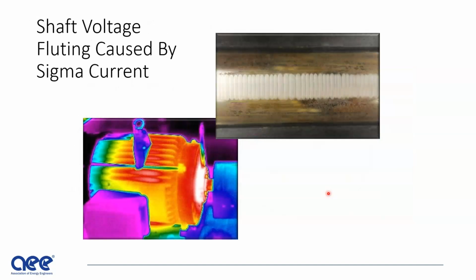This is an example of what it looks like when you have shaft current. Here you see a bearing that is running very hot, and it's because of this race inside the bearing. You see this fluting, and this fluting is an indicator of shaft voltage or current riding through the bearings, causing an incredible amount of friction.